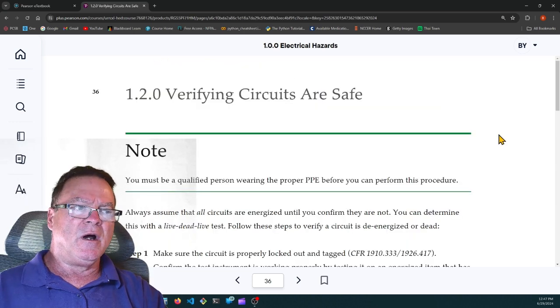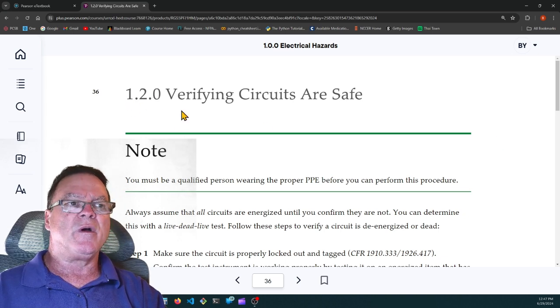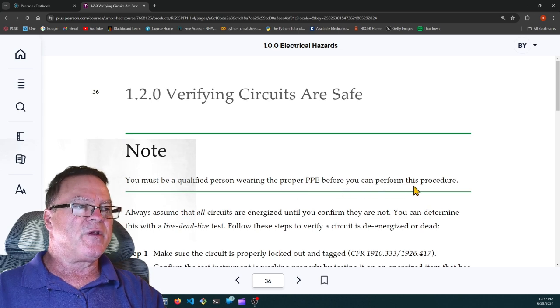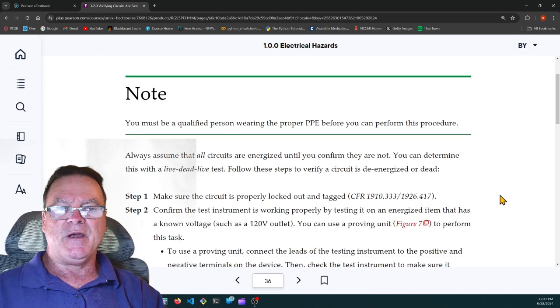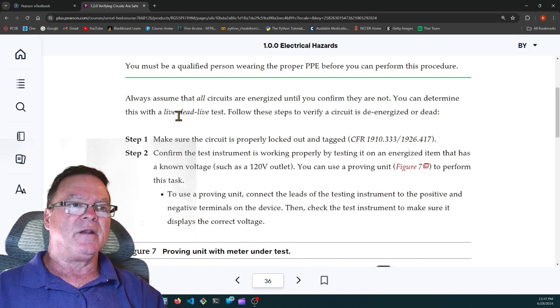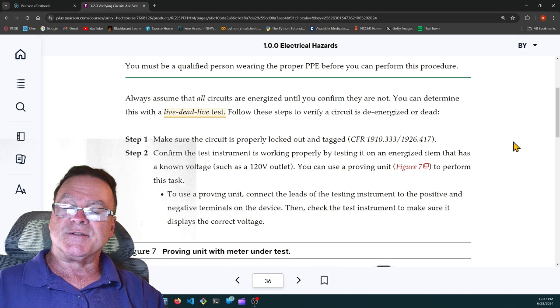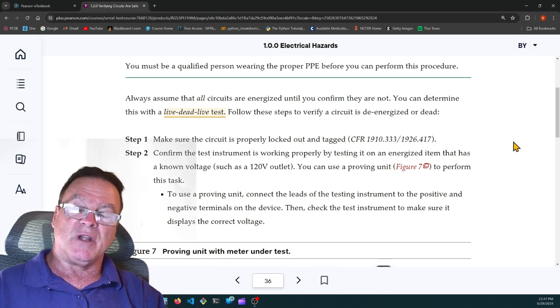26102, electrical safety. Section 1.2.0, verifying circuits are safe. Note, you must be a qualified person wearing the proper personal protective equipment before you can perform this procedure. And then they go on and talk about a live, dead, live test. I believe that is a highlight. Live, dead, live. You make sure your meter's good by testing it on a known live circuit.